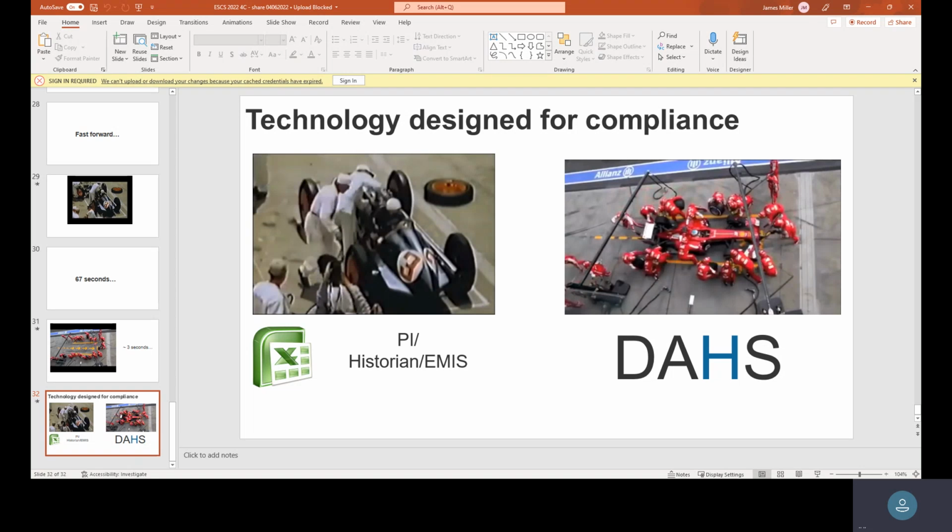There are also ways to throw up suspects and say, this is kind of outside of a window of normal operation, and that's a good thing for operations. If things are starting to drift up or too low, and you're like, wait a minute, what's going on? You can dig into it further and say, oh, we're having trouble downstream someplace else with different equipment, and it's affecting this. Being able to look at those trends and set bands where normal operation falls and get flags, to me, that's the big advantage for day-to-day operations. Not to mention flat lines, or instruments that just stop reporting or continue to report the same value over and over again. You can put flatline adjustments on there to say, I'm expecting a certain amount of variation over this period of time, and if I don't see that, let's raise a flag and make sure the instrument isn't failing. Again, it helps you be more proactive and get ahead of downtime the best you can.